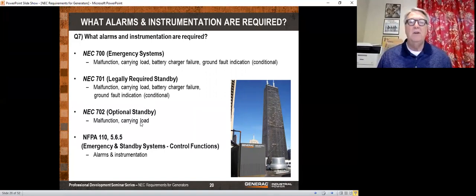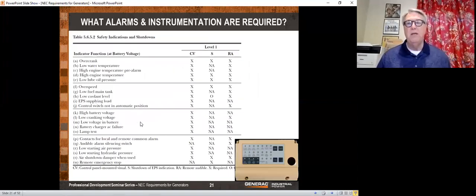If you have NEC 700 or NEC 701, the National Electrical Code only requires the alarms and instrumentation that we show there. But if you have an emergency or a legally required system, you must also meet NFPA 110. Now, we're going to talk in detail about NFPA 110 next week, but right now, let me just point you to this. If they want to make this difficult for you, see where it says level 1? That's basically the same thing as an emergency generator. And there's a level 2, which is not shown on the slide, which is the same thing as a legally required generator.